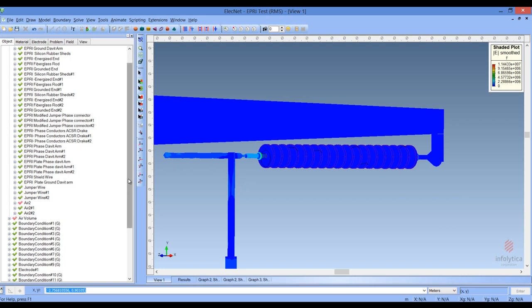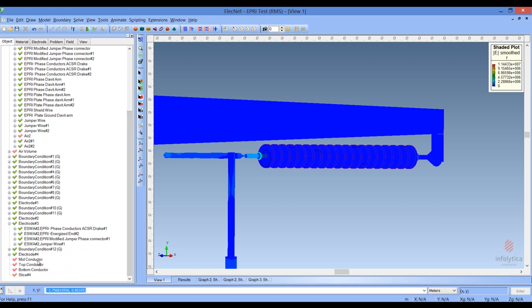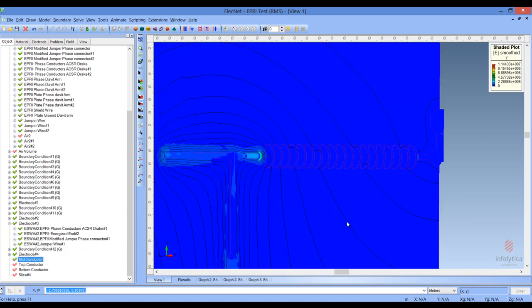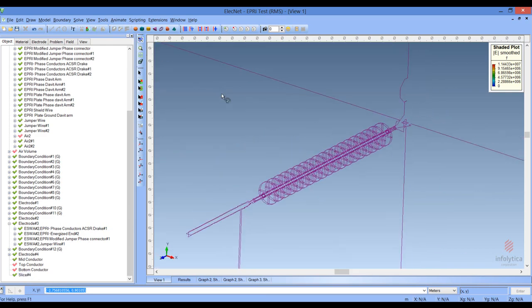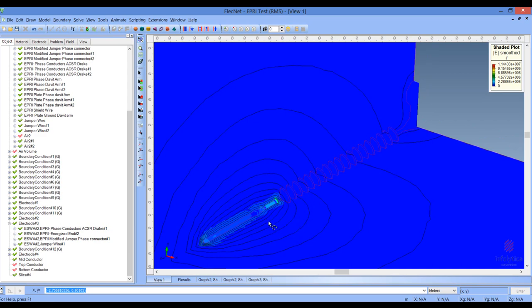We can also view on slices. Let me bring up some slices. This particular slice is a vertical slice through the sheds and through the conductor, including the energized conductor. The second slice is orthogonal to the first. Here we can see a line showing where that slice is located, so you can see the fields, the equipotential flux, and the electric stress in that region.